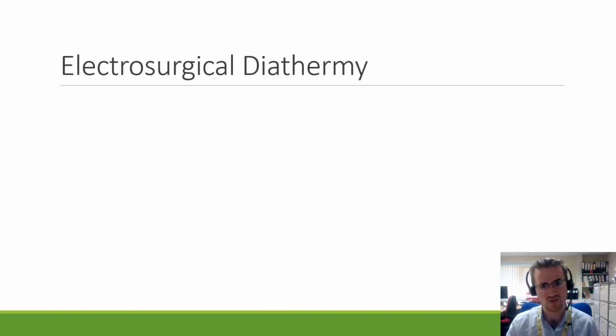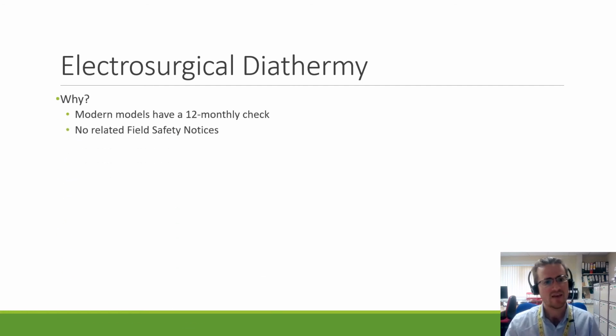And going on to the electrosurgical diathermy. Why these? Well, we're addressing the 6 monthly PMs that other, modern models seem to have a 12 monthly check on. Couldn't understand why particularly, and maybe it was something related to something from the 80s with old terrible capacitors that didn't last very long. We looked at field safety notices, couldn't find anything that indicated that they should be 6 months, like as with the Genius 3 thermometers.